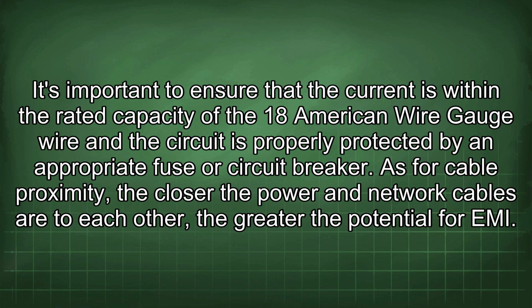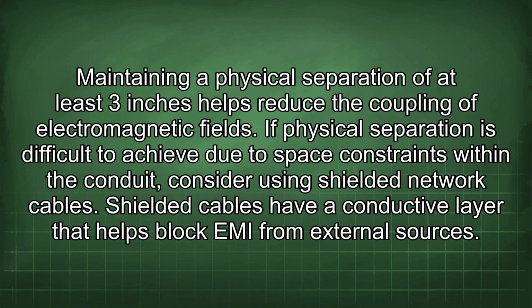As for cable proximity, the closer the power and network cables are to each other, the greater the potential for EMI. Maintaining a physical separation of at least 3 inches helps reduce the coupling of electromagnetic fields. If physical separation is difficult to achieve due to space constraints within the conduit, consider using shielded network cables. Shielded cables have a conductive layer that helps block EMI from external sources.